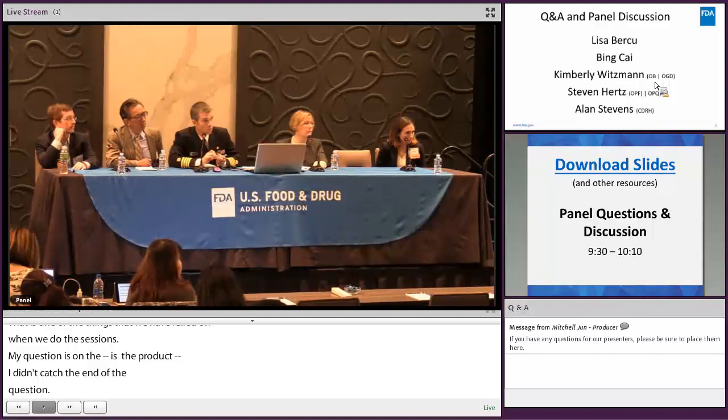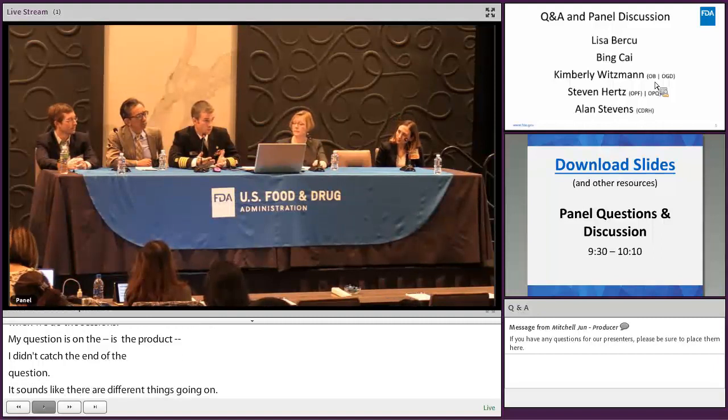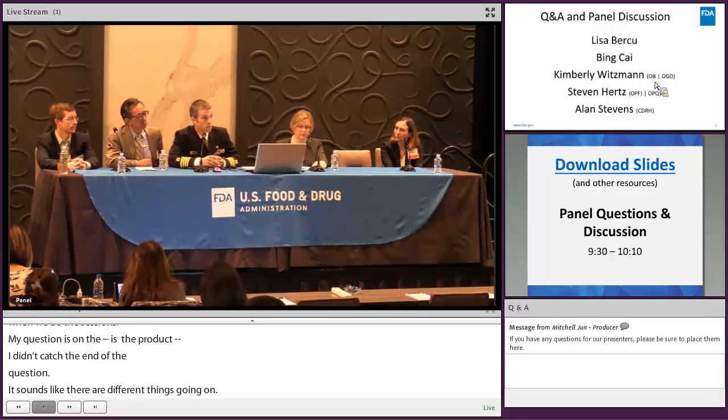Gotcha. It sounds like there are different things going on for your product. If we're looking at a device that's delivering a drug, and the requirements of that device are to deliver a certain volume per time or per injection, then from the engineering standpoint we're looking to see that you have evidence to verify and validate that the device is doing what you intended. Whether the suspension is acting appropriately or not is a drug quality issue. That would not be something that we in CDRH would be addressing.